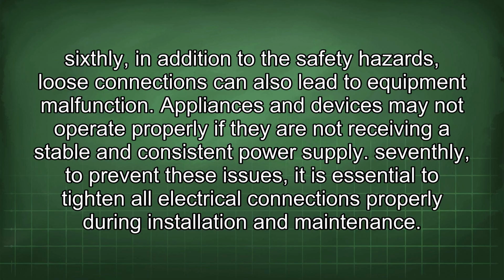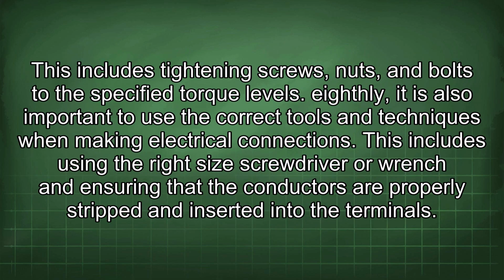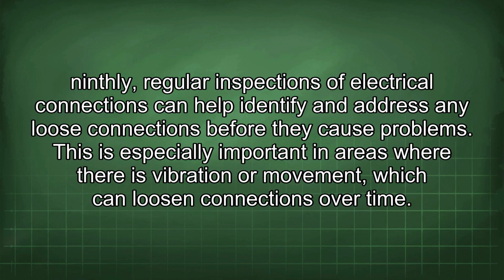Seventhly, to prevent these issues, it is essential to tighten all electrical connections properly during installation and maintenance. This includes tightening screws, nuts, and bolts to the specified torque levels. Eighthly, it is also important to use the correct tools and techniques when making electrical connections. This includes using the right size screwdriver or wrench and ensuring that the conductors are properly stripped and inserted into the terminals. Ninthly, regular inspections of electrical connections can help identify and address any loose connections before they cause problems.